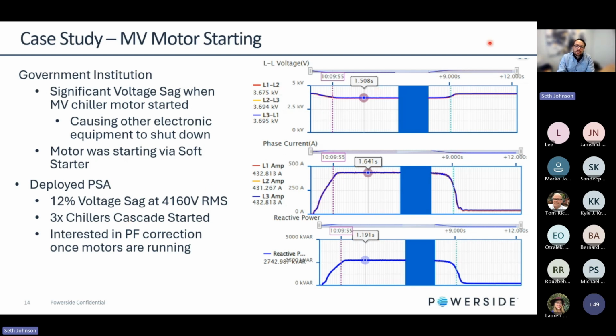So these are actual images that we got through QubeScan of the event that occurred during the motor starting of this soft-started medium voltage chiller motor. And you can see we're down to 3.6 kV for voltage down here. So certainly a significant voltage drop. And so they asked us, well, what can you do for us in terms of a correction solution?